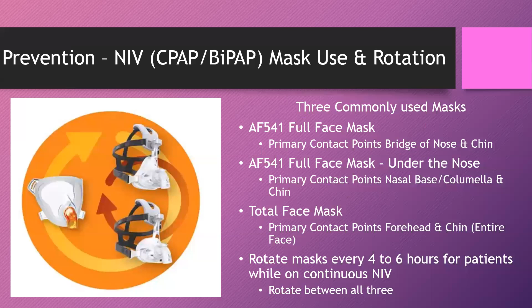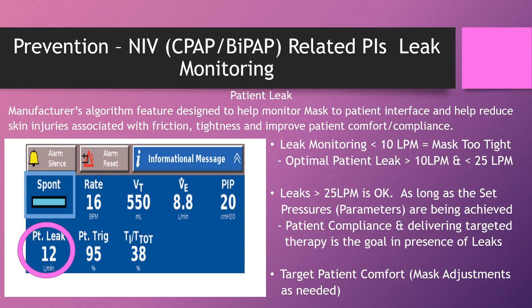So now we're going to talk about leak monitoring. So the manufacturer's algorithm feature is designed to help monitor the mask to patient interface and help reduce skin injuries associated with friction, tightness, and improve patient comfort and compliance. So leak monitoring less than 10 LPM means the mask is too tight. The optimal patient leak is greater than 10 LPM and less than 25 LPM. So we want to be between 10 and 25. But leaks greater than 25 is okay, as long as the set pressures or parameters are being achieved, and patient compliance and delivering targeted therapy is the goal in presence of leaks.